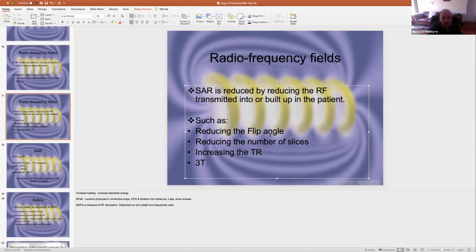3 Tesla is more SAR than 1.5 Tesla. So if you've got a 3 Tesla and you're worried about heating the patient up too much, put them on the 1.5 Tesla machine. The higher the magnetic field strength, the higher the SAR.